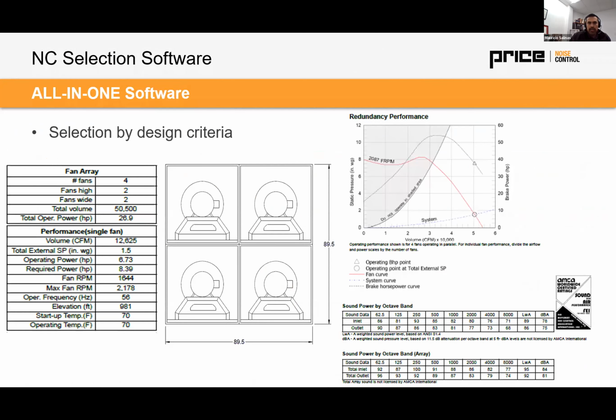There is another way, selection by design criteria. You might have sound power levels of a fan. This is an array of 4 fans pushing 50,000 CFM. They have a total external pressure drop that the fan can overcome of 1.5 inches. And you have the array of silencers for the outlet. We're going to look at the discharge, have that sound power level per octave band, and you want to know how quiet you can get it, right? So in this case, the way to read this is sound power in one number.